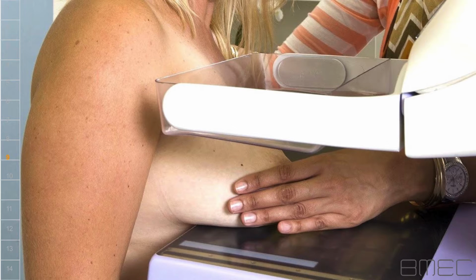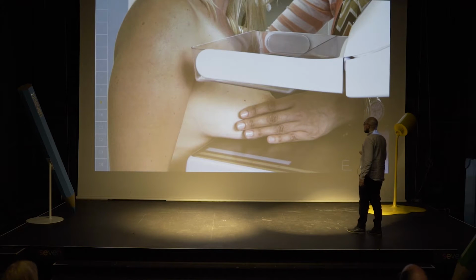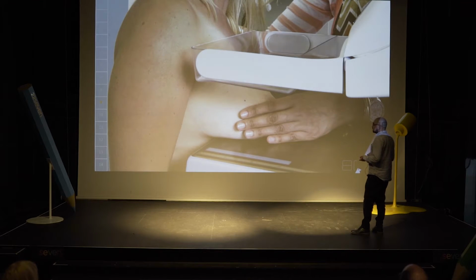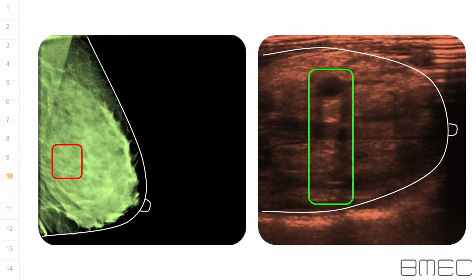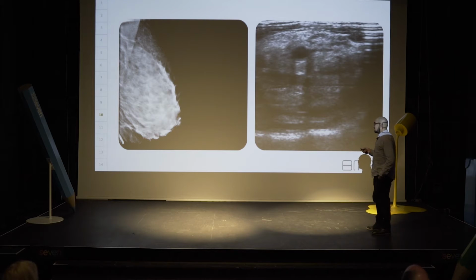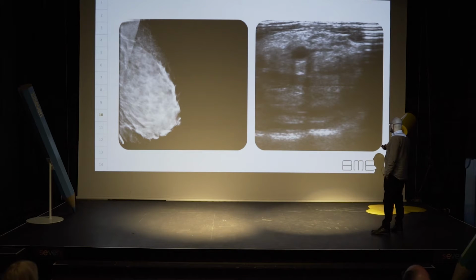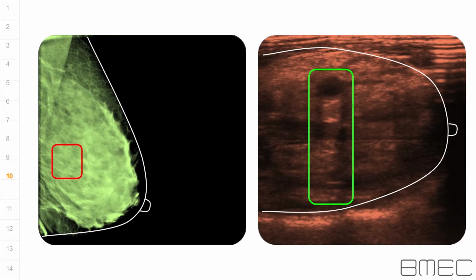So this image shows the wider element probe that we put together, at the start of a clinical exam. It's worth noting that this probe was longer than the handheld ultrasound probe, but not as long as the multiplexer probe. It also wasn't long enough to image very large breasts. This is an X-ray and an ultrasound image that was acquired during a clinical trial using the wider element probe. What's truly amazing here is that on the X-ray there are no suspicious lesions visible, but on the ultrasound there is clearly a cyst present, and you can see that over here. So this was truly great, because it clearly demonstrated the capability of the technology to improve breast cancer detection.